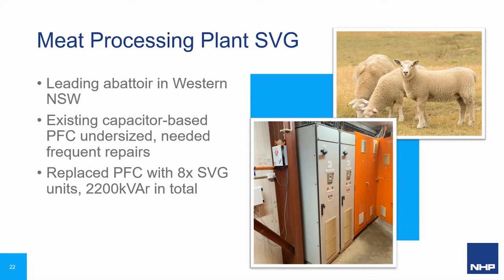Now, initially, I was actually out there assisting the customer scoping a service regime or shutdown for their LV circuit breakers and cap-based correction systems that are existing on their site. Out of that, once the servicing was completed, it actually highlighted multiple issues across their cap-based systems and their circuit breakers as well.